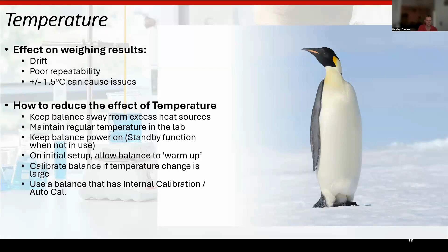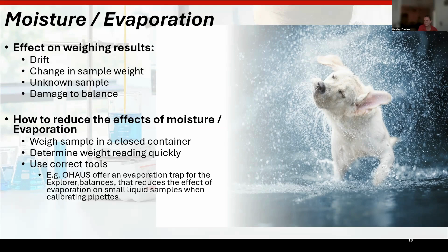Moisture and evaporation. It's especially important to watch out for when you're weighing liquids or small samples. As the sample evaporates, the weight can drift and the balance itself could even be damaged. Always try to weigh quickly. Use closed containers where possible, and make sure you use the right tools. For example, some Ohaus balances, such as the Explorer models, have special evaporation traps to minimize the issue.